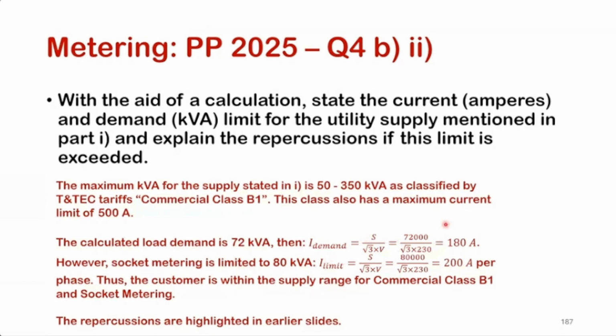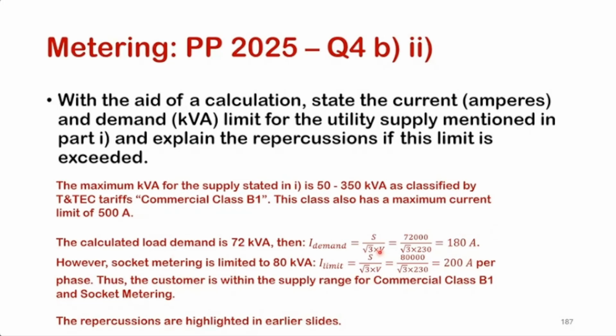Per phase, we join. So, socket type metering is limited to 80 kVA. So the limit for socket metering, you prove that because the number we say is 200 amps per phase. So how do we get that? It's really 80 kVA divided by root 3 and 230, which is 200 amps per phase. So the customer is within the supply range for the commercial class B1 and socket meter.